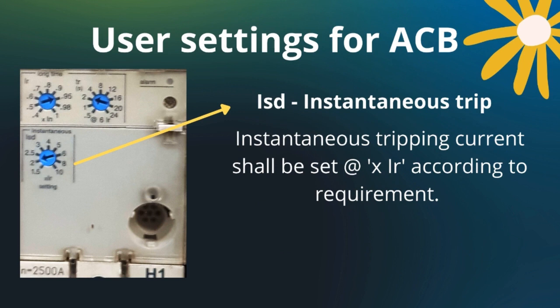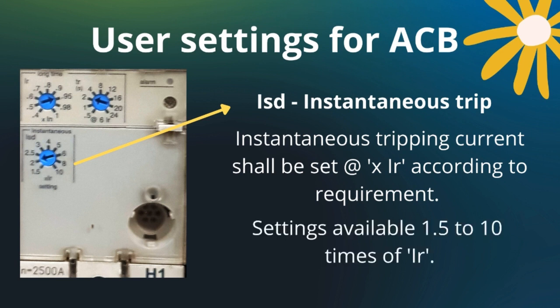ISD, instantaneous trip. Instantaneous tripping current shall be set at the multiplication of long time current according to requirement. Settings range available from 1.5 times to 10 times of the long time current.